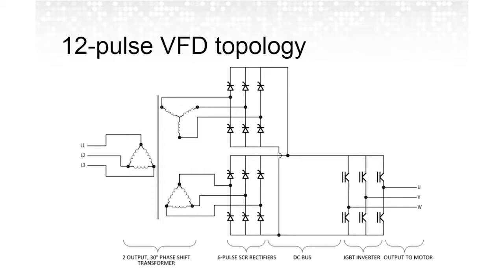So as a result, with this phase shift of 30 degrees between the 2 inputs to the rectifiers, we can effectively cancel certain order harmonics and reduce the overall total harmonic distortion associated with this design down to 12 to 18%. While this goes a long way towards the issue of harmonic distortion, there is a significant downside. As you can see, this is a much more complex design, and as a result, with all these additional components, the physical size is going to be bigger and the cost is going to be more. It's not unusual for a 12-pulse VFD to be twice the cost of a 6-pulse VFD with line reactors.